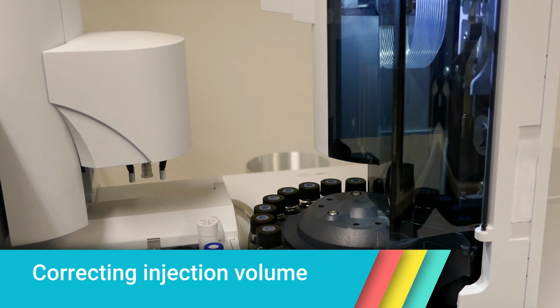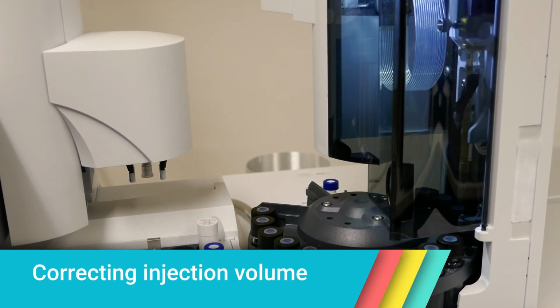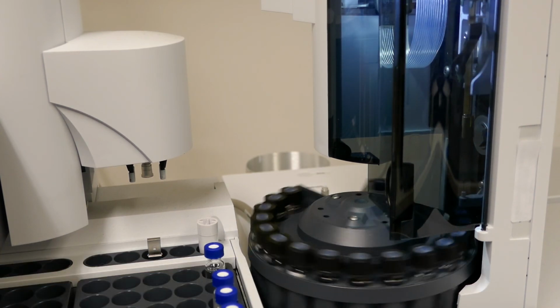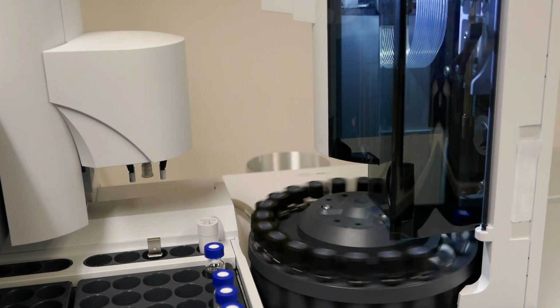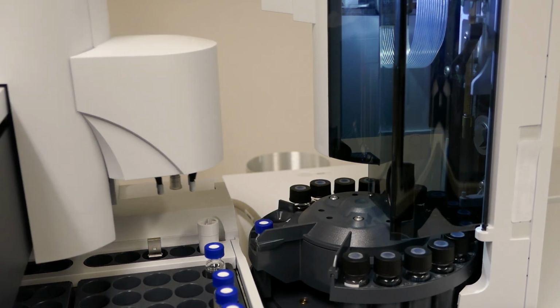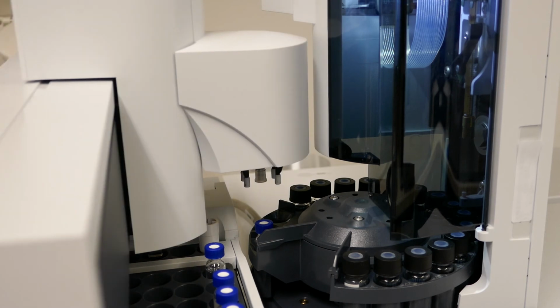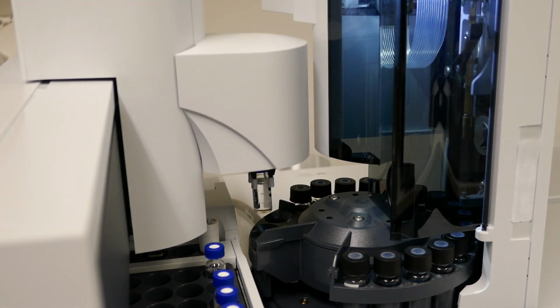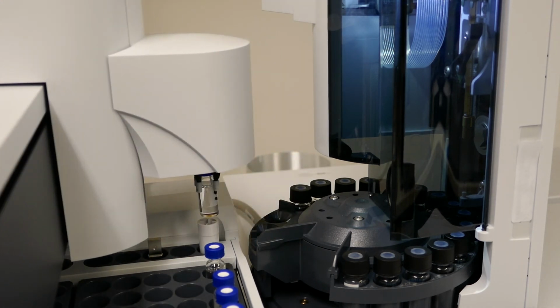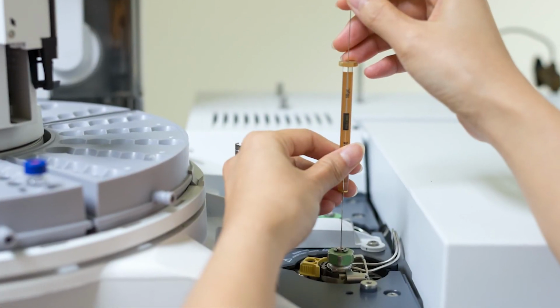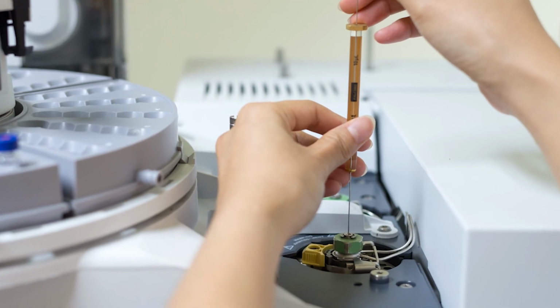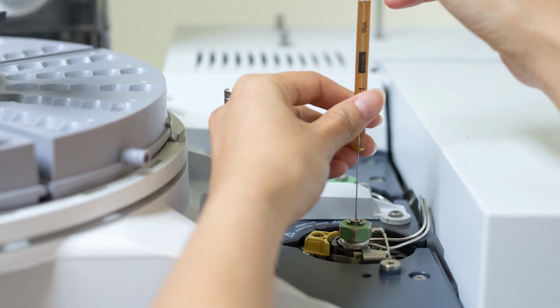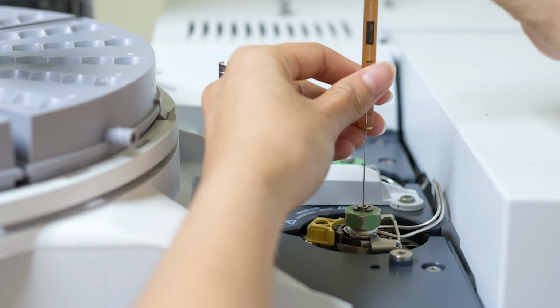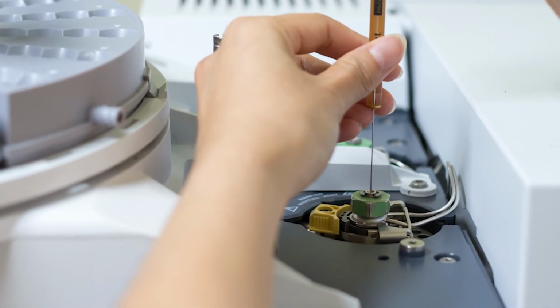Correcting for variations in injection volume. Up to now, it has been assumed that the injection volume was held constant throughout calibration and analysis. This is often not the case in actual laboratory practice, especially when the chromatograph is not equipped with an auto-sampler. Since most methods measure the analyte concentration, rather than its absolute amount, the injection volume is central to quantification and any inadvertent or deliberate variation in this volume must be considered.